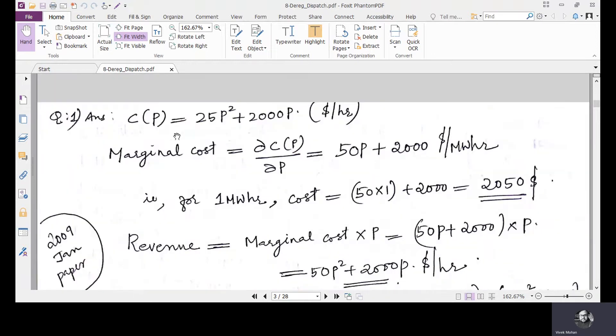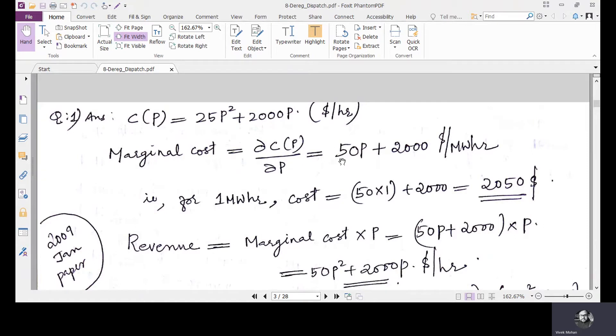The fuel cost is given as 25p² + 2000p dollars per hour. The marginal cost is the cost for the next increment — that is, dC/dp, the derivative of cost with respect to change in p. Taking the derivative gives 50p + 2000. The unit is dollars per megawatt hour, which means this is the energy cost — this is the marginal cost.